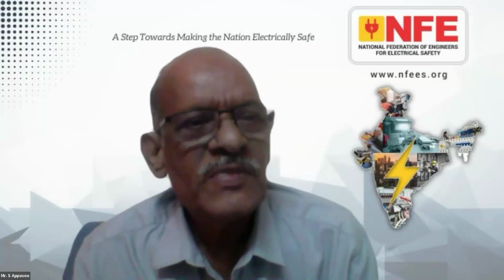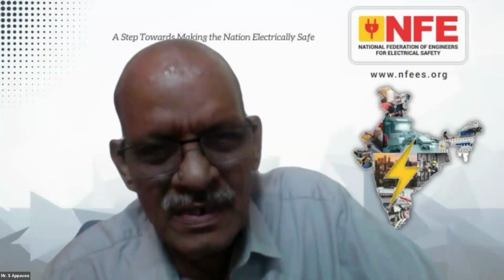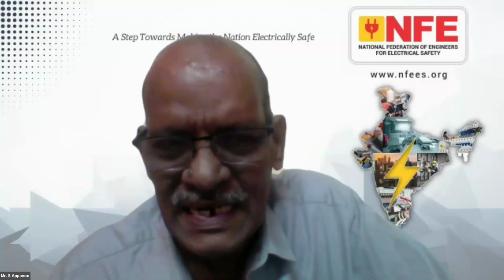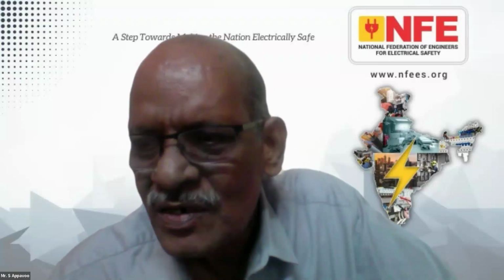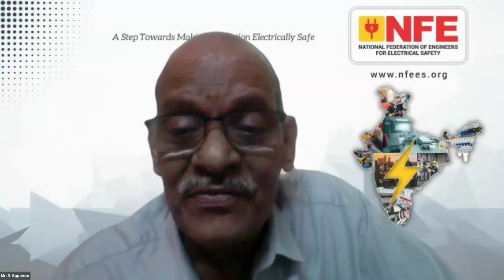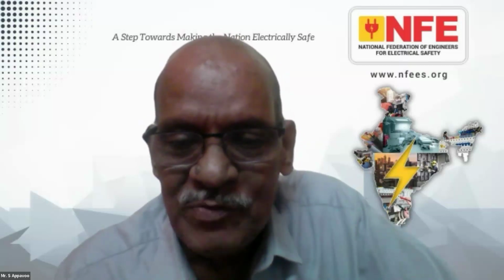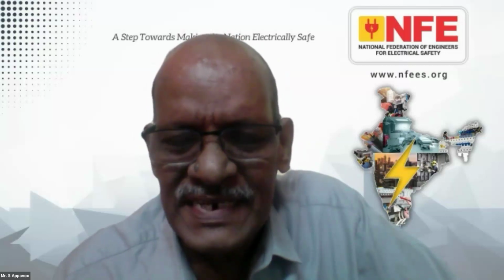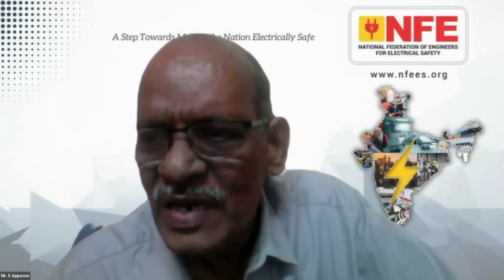Abhishek, I would like to add one thing. Mr. Goyal, what is the location of this active filter? Is it near the transformer or between the transformer and the load? What is the exact electrical location, where it is connected? That is, the connection point of the active harmonic filter, from the transformer to the panel or after the panel, load side or supply side. It is on the 415 volt LT side, after the panel. My connection is on 33 kV. We have used a 4 MVA transformer, 33 kV to 415 V, and we use the HF on 415 volt.